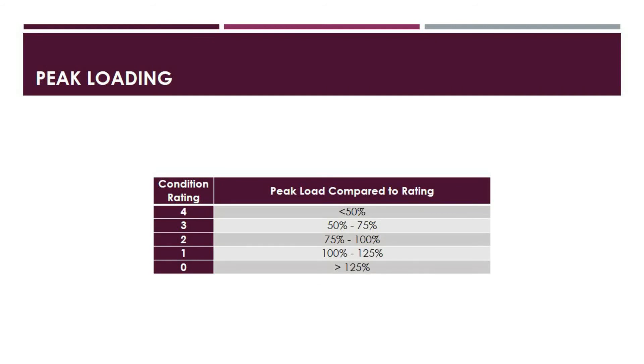The second category is peak loading with respect to the nameplate transformer rating. A rating of 4 is given for peak load less than 50% of its rating. A rating of 3 is given for peak load more than 50% and up to 75% of its rating. A rating of 2 is given for peak load between 75% to 100%. A rating of 1 is for peak load more than 100% but less than 125%. And if the peak load is greater than 125%, we assign a rating of 0.